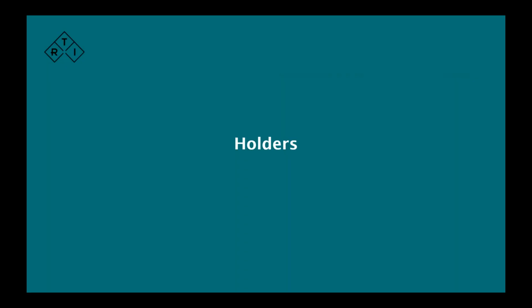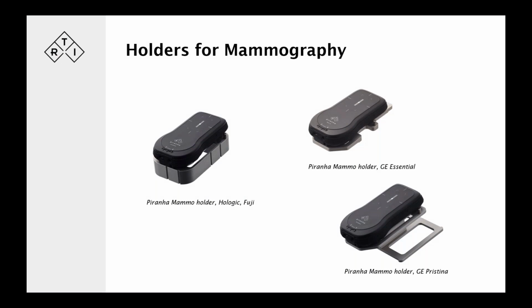And to be able to cope with everything, of course, you need holders to get the meters in the right position. For mammography, it's holders for the Piranha. We have one that fits Hologic and Fuji, getting the Piranha into the correct reference height for those. GE Essential has one holder as well for that purpose, so it gets the right height and also the right position, as we do for the GE Pristina. So those holders are designed together with the manufacturers, GE and Hologic and Fuji. So those are available to make that job easier also. Don't have to measure, just get the holder, and with that holder you have the right reference height.